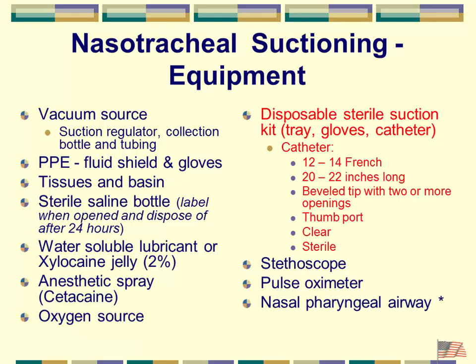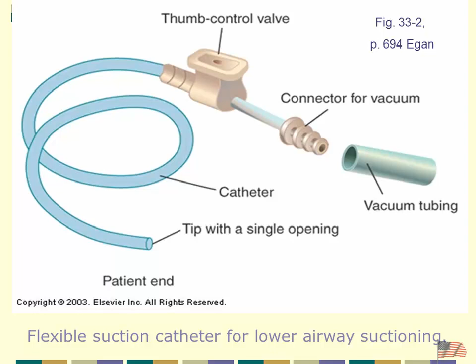And again, we'll talk about a nasopharyngeal airway. If you're doing repetitive nasotracheal suctioning, it makes sense to put a nasopharyngeal airway in and just pass it through that airway as opposed to running it through the person's nose each time. So again, the design is I have my vacuum hooked up to the connector, and as I put my thumb over the end of the thumb control valve, vacuum is applied at the very tip, and we can apply it to the airway. So here's the sterile suction kit.